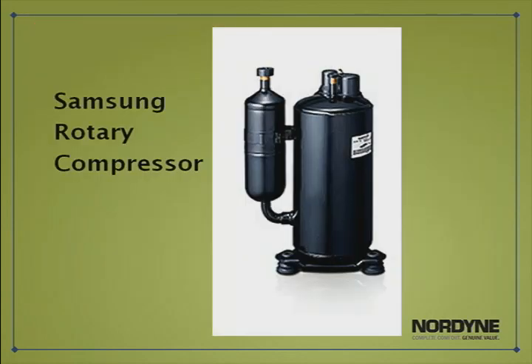The condensers use a Samsung rotary compressor and use 410A refrigerant. The speed of the compressor is determined by the inverter. When troubleshooting the compressor, you'll have to use an ohm meter and test for short, open, or grounded windings. The compressor does not have an internal overload. The voltage control signals from the inverter to the compressor are pulse width modulated. This type of signal cannot be measured with a standard voltmeter. Since the inverter controls the speed of the compressor, if the inverter fails, it should be replaced.